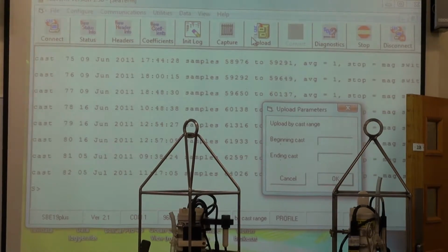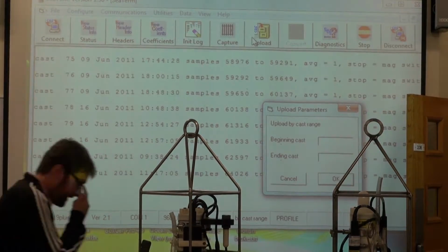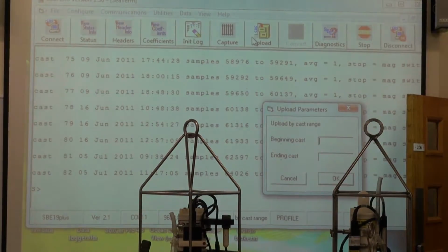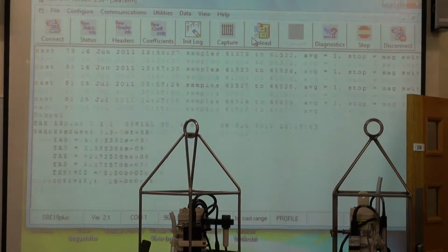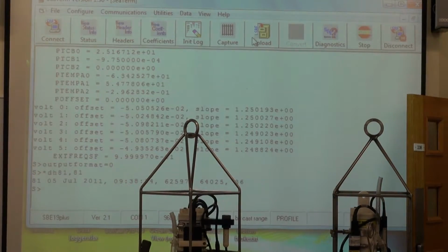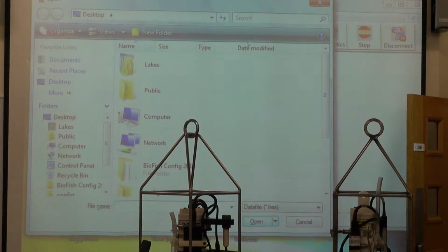So, when you've been out in the field and taken some casts, always make sure you download it as soon as you can, because you never know what someone else is going to do with the instrument. They might come along and intentionally or not delete all the casts that are there, and then you've lost your data forever. The software is set up on all the machines, I think, to select the cast range, and then it will download them all. So we'll just do like the last two. So we start with cast 81, finish with cast 82. Select OK, and it'll ask us for a place to save it.